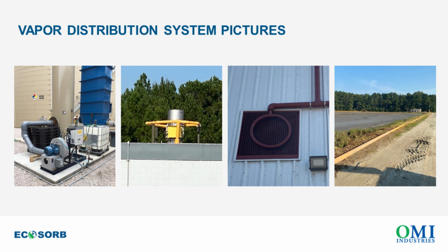So our vapor goes into that exhaust stack and then treats it. We put a nozzle on the inside so that we make sure we get distribution and contact inside that stack. Move to the right, you'll see a Venturi exhaust, and we've got the EcoSorb ducting there. It's yellow. We've got vapor ports that actually feed into where the Venturi exhaust pulls in the outside air, so we make sure we get contact with all the gases.